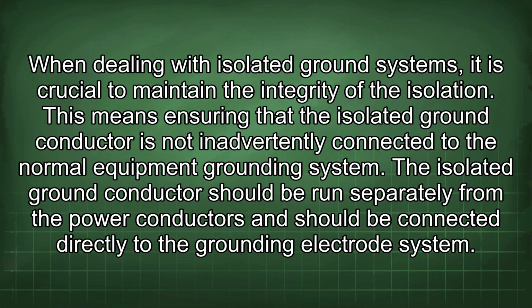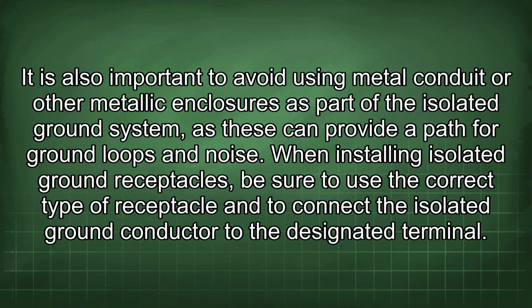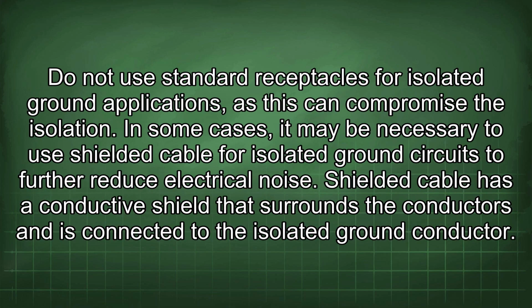The isolated ground conductor should be run separately from the power conductors and should be connected directly to the grounding electrode system. It is also important to avoid using metal conduit or other metallic enclosures as part of the isolated ground system, as these can provide a path for ground loops and noise. When installing isolated ground receptacles, be sure to use the correct type of receptacle and to connect the isolated ground conductor to the designated terminal. Do not use standard receptacles for isolated ground applications, as this can compromise the isolation.